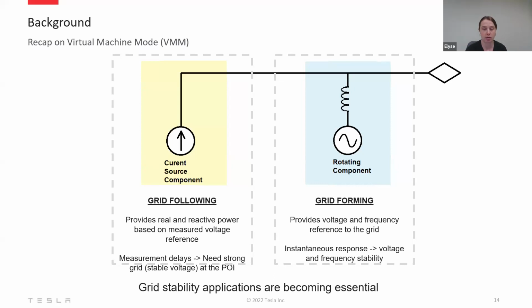It's important to note that this is not a new hardware requirement. Tesla's inverters are virtual machine mode capable, and the feature is enabled by just a settings change. When both of these elements are operating in parallel, the resulting output provides the same real and reactive power dispatch services as standard grid following modes, along with the grid stabilizing services made available by the virtual machine element. So the system can respond at high speed to produce active power response proportional to the rate of change of frequency following some network event, or produce reactive power to improve the voltage waveform.